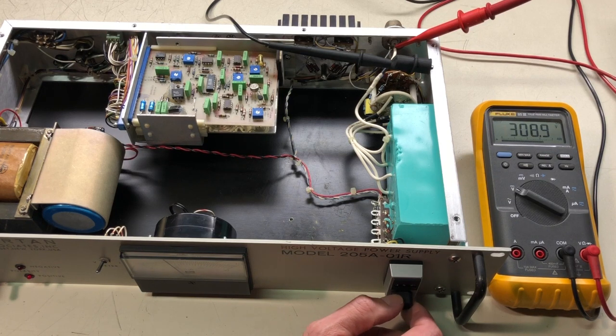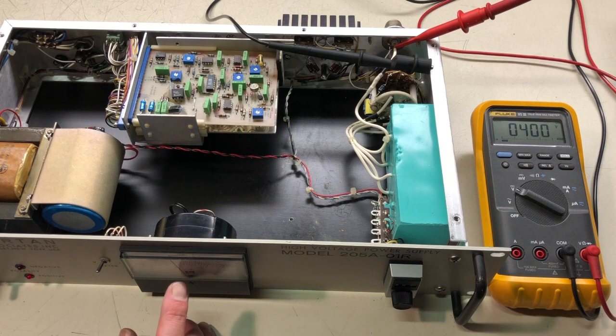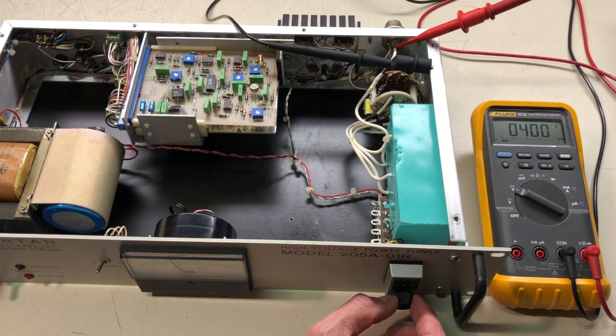Let's go up. Go to 400. Jump up a little bit here. Right there, 400. Yeah, it's just a tiny bit under 400. Just the width of the needle under 400 on the meter. So, not bad. Go to 600. Yep, 600 on the meter. Looks like it's reading just ever so slightly under 600 on the meter, but very, very close.